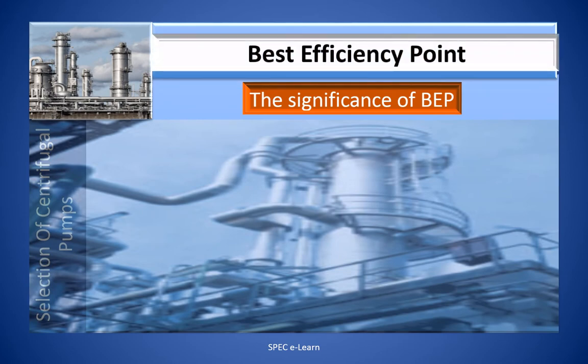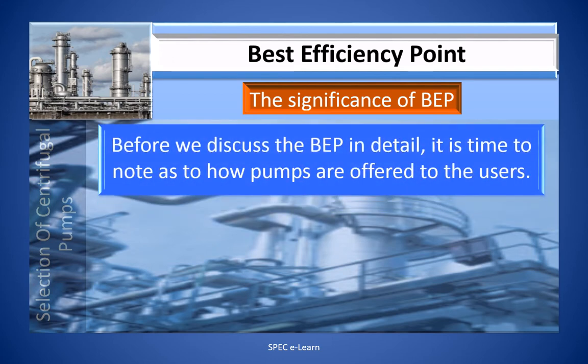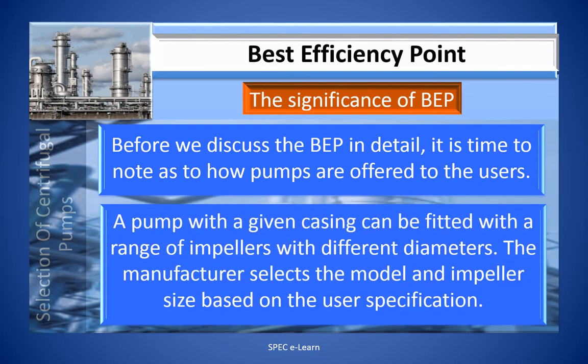Before discussing BEP in detail, it is important to note how pumps are offered to users. A pump carries a model number which indicates the pump or casing size. A pump with a given casing can be fitted with a range of impellers with different diameters, and the manufacturer selects the model and impeller size based on the user specification. The efficiency of the pump varies with the impeller diameter chosen.